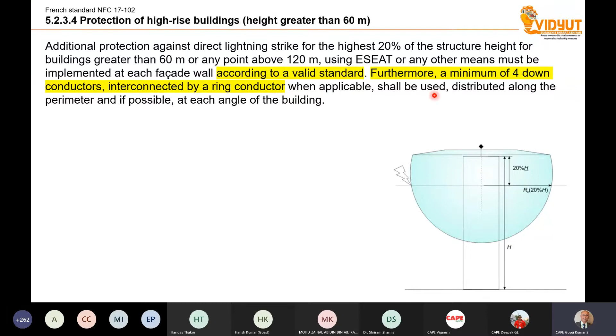Actually, this is very clever wording. The only valid standard is the IEC 62305. What the NFC standard says is that for a high-rise building, you make an equipotential bonding, or you make a connection according to a valid standard, which is the IEC standard. Furthermore, a minimum of 4 down conductors interconnected by a ring conductor, when applicable, shall be used. Unfortunately, these are not done in India.